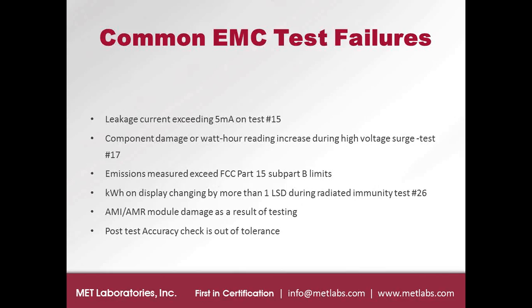The most common EMC failure we see here in the lab is leakage current exceeding 5 milliamps. This is the insulation test, which is part of the series test that Jim alluded to. We test for the insulation between various coupling paths in the circuitry. We test the product at 2500 volts RMS for 1 minute, and we measure the leakage current, which is required to be 5 milliamps or less. Most times this is the test that a lot of products fail, and we'll get to why in the next slide.